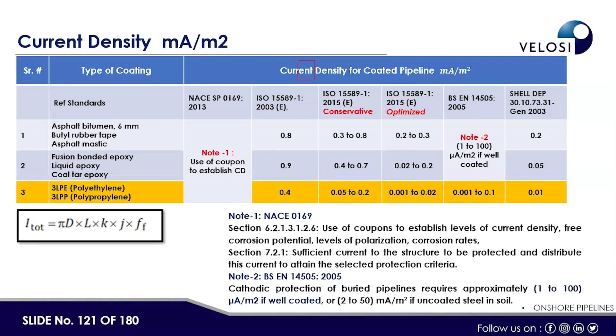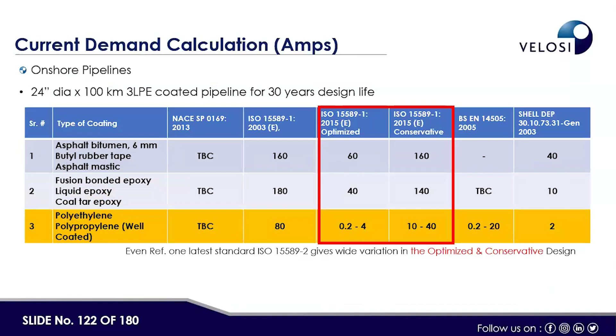If you have asphalt coated pipelines, as per ISO 15589, for a 30-year life that requires 60 ampere current. If we go with the conservative design, it requires 160 ampere. So you need a transformer rectifier unit of 160 ampere to protect your pipeline, which is asphalt or bitumen coated. But the same pipeline, if it is 3-layer polyethylene, will require only 10 to 40 amperes. So here we will calculate the current requirement.